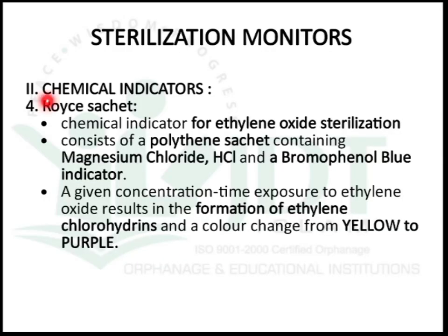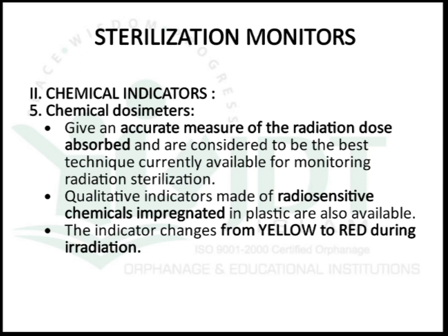Royce sachets are chemical indicators used for ethylene oxide sterilization. They consist of a polyethylene sachet containing magnesium chloride, HCl, and bromophenol blue indicator. A given concentration and time of exposure to ethylene oxide results in the formation of ethylene chlorohydrin, which changes the color from yellow to purple.